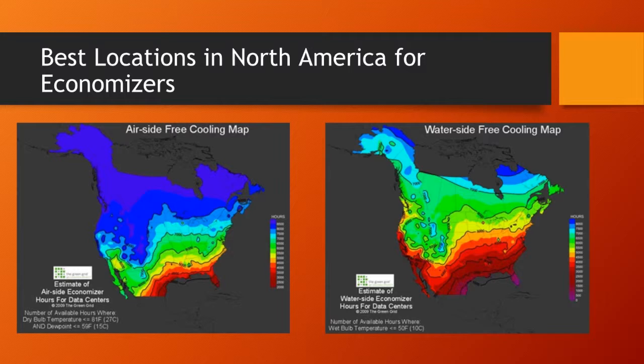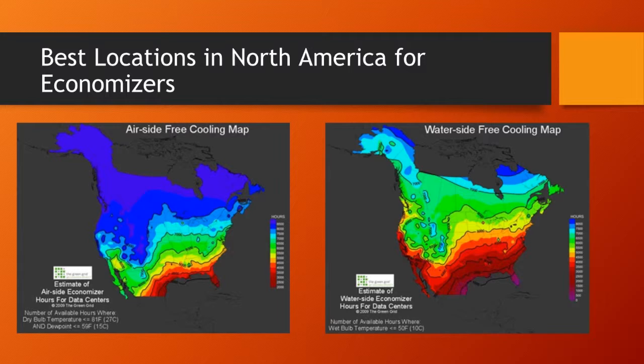So here's a map of North America with your best locations for an economizer. Over here on the left side of the screen, you're going to see it's our air side free cooling map. Down in the south, you're going to see that it's red, which is where you can run like the least amount of hours. It's just not a good spot to be using the air side economizer. You're not going to be efficient. You're going to be probably wasting more energy than saving. You can see up in the northwest is your main reason you're going to be running that air side economizer. They're going to have mild temperatures. You can run that up to 8,500 hours, so it's a great option for your system.